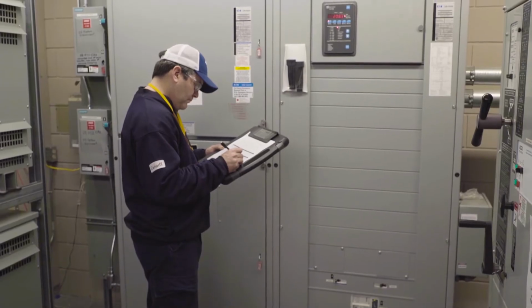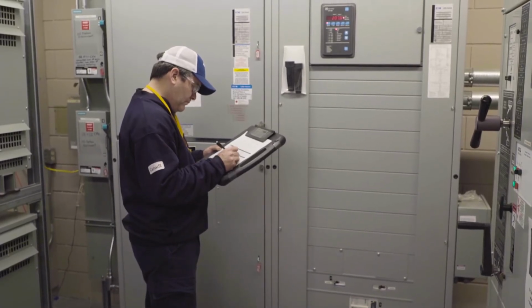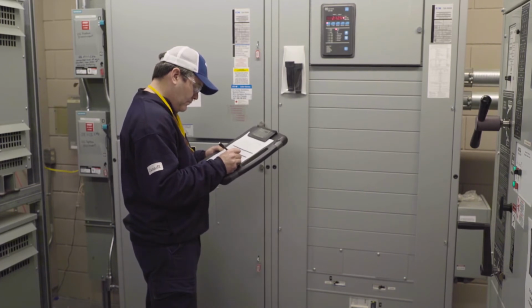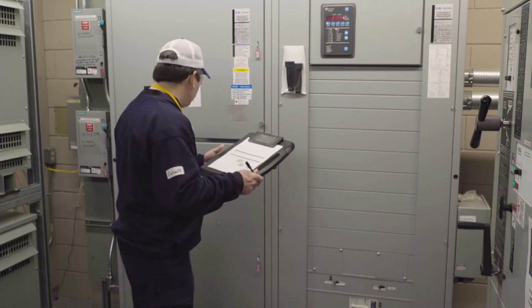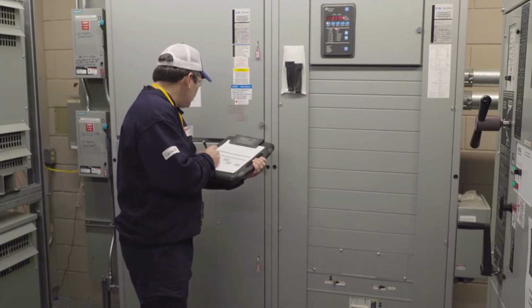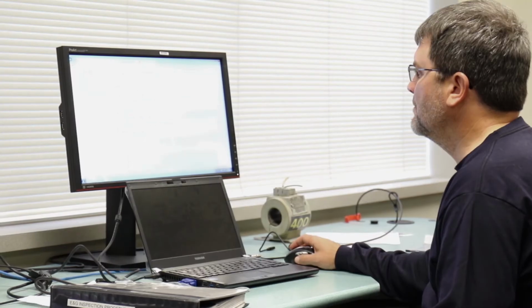When completing your inspection, 1. Ensure that all relevant information has been noted and documented on the worksheets. 2. Indicate the rating of the installation as found at the site. Verification of the billing multiplier when the inspector returns back to the utility billing office may require this rating to change, should a problem be discovered with the billing multiplier.